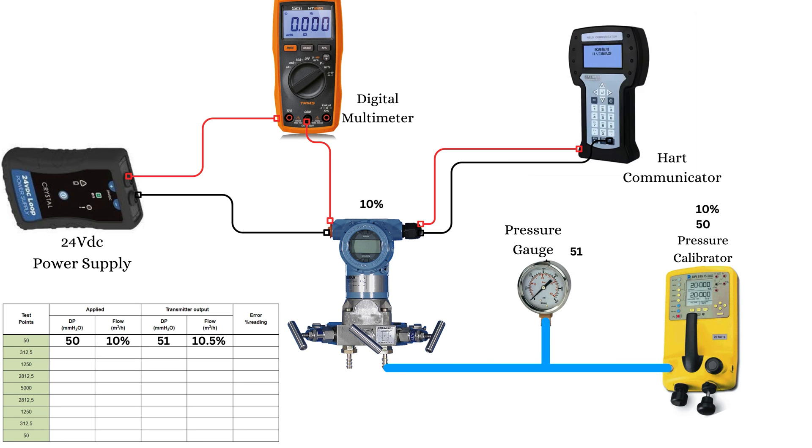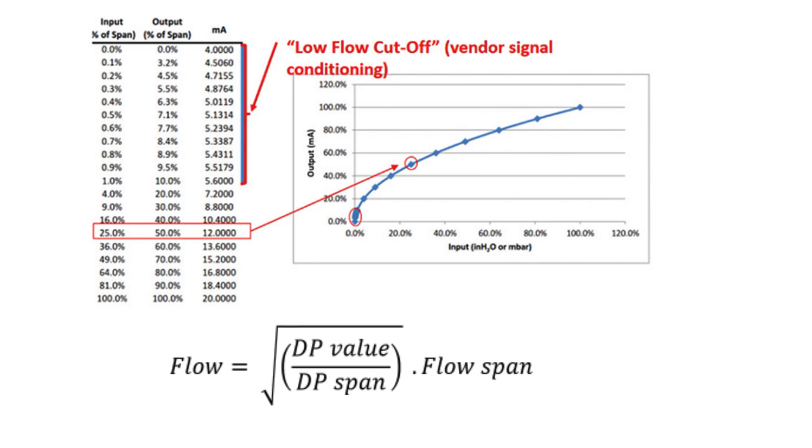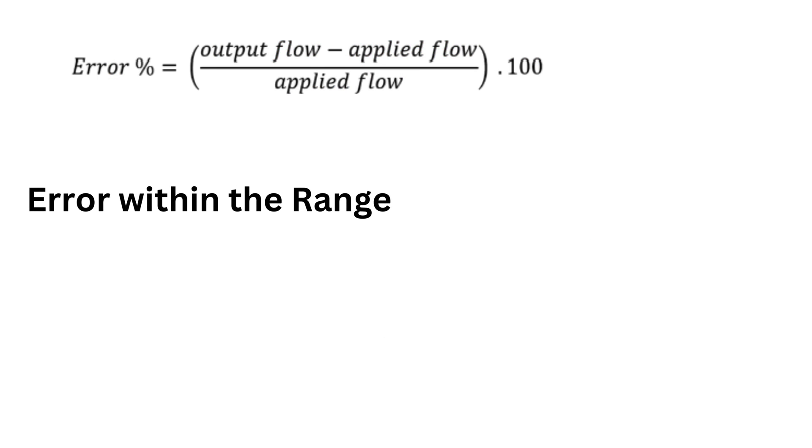As the square root extraction is done by the transmitter, its output represents the flow rate. To calculate the error on the output, we will have to compare the measured flow rate with the applied flow rate. As we can only apply a DP, we will have to calculate the applied flow with the following formula. Do this calculation for every test point and fill in the flow rates in the third column, applied flow.